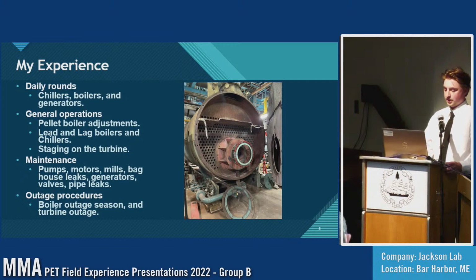which chiller we wanted to run. We also had a single stage impulse turbine. It was a Dresser Rand. It was pretty small, and it would only run at certain steam loads. So when we had high steam loads, we could run the steam turbine as our reducing station. But when the steam load would drop off during lunchtime or during the nighttime, we would lose the turbine. So we took that down for an outage to try to put a new nozzle block in it so that we could run it at lower steam loads as well.